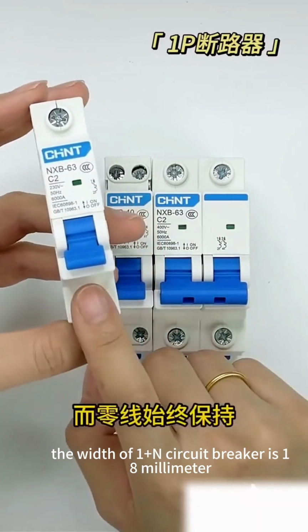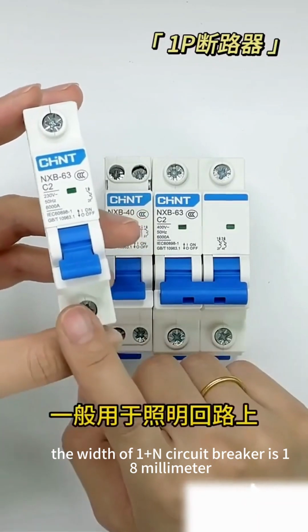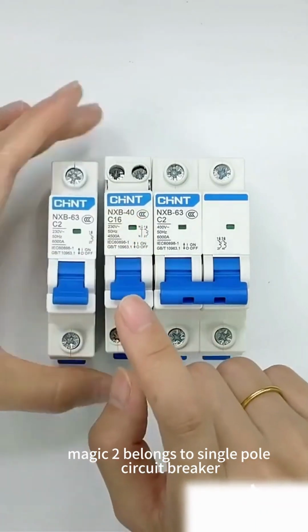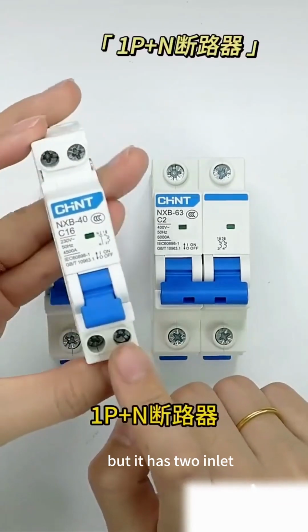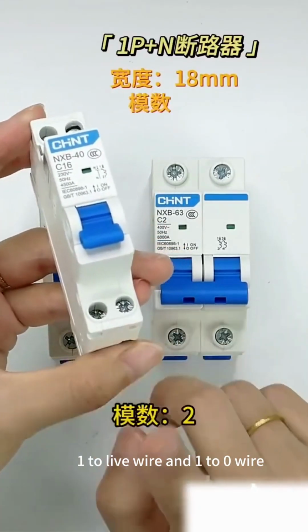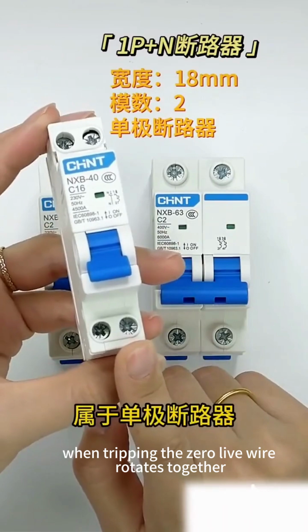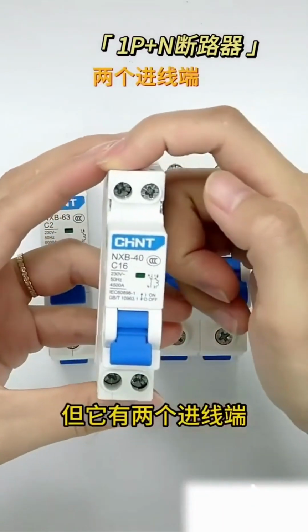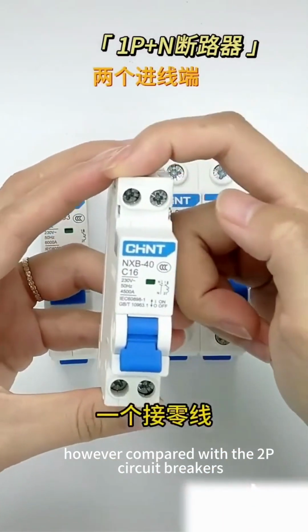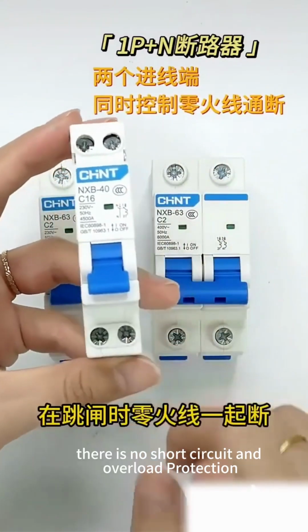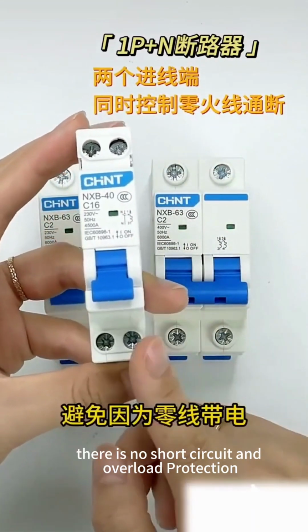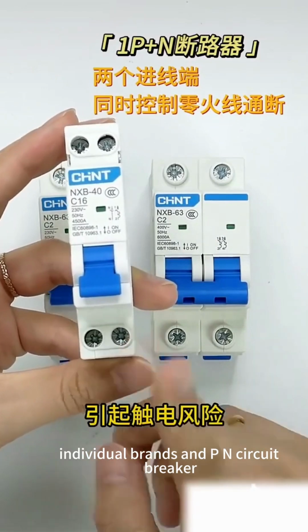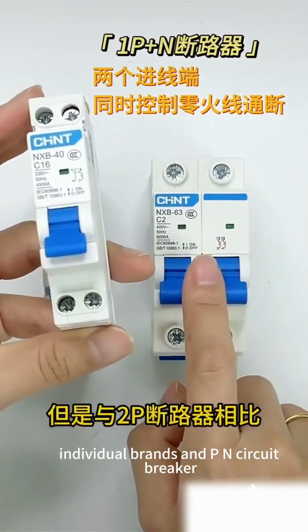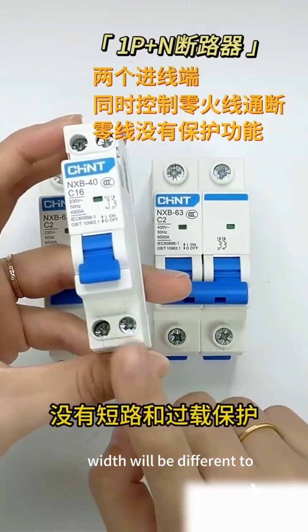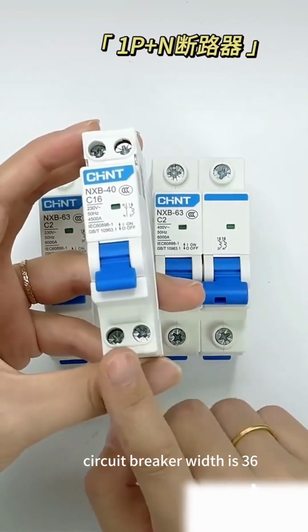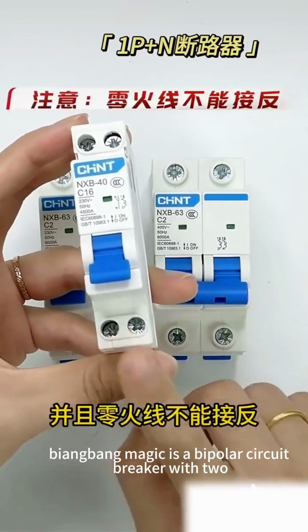The width of one P plus N circuit breaker is 18 mm. It also belongs to the single pole circuit breakers, but it has two inlet ends, one for the live wire and one for the neutral wire. When tripping, the neutral and live wires are both disconnected. However, compared with the 2P circuit breakers, the neutral line can only be cut off. There is no short circuit and overload protection, and the wiring cannot be reversed. The width of P plus N circuit breakers will differ between individual brands. The 2P circuit breaker width is 36 mm.